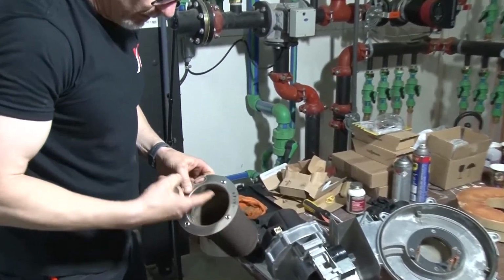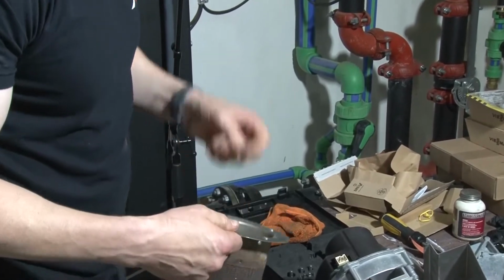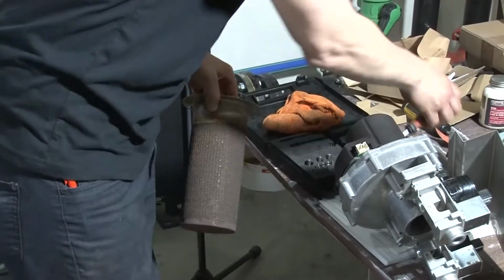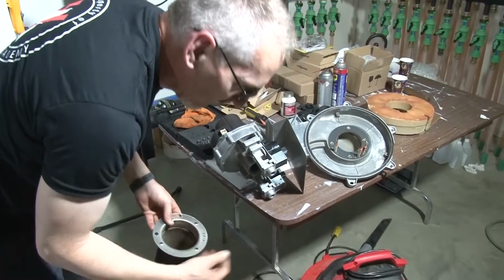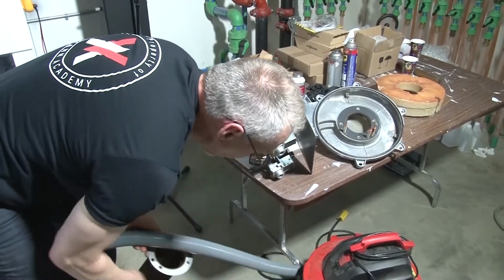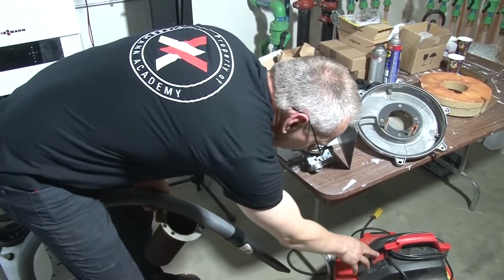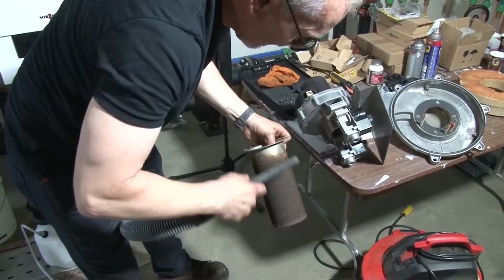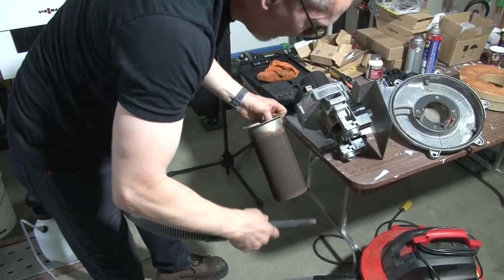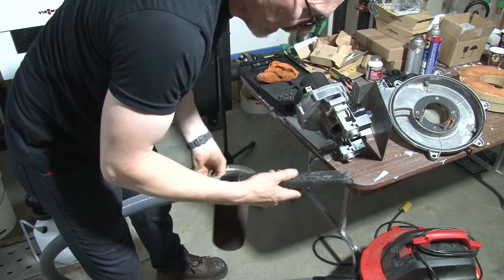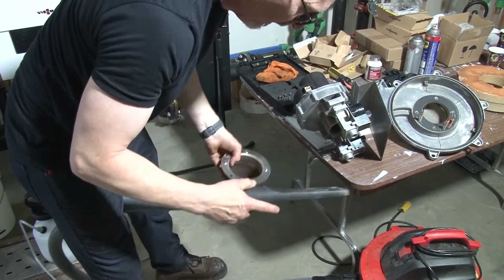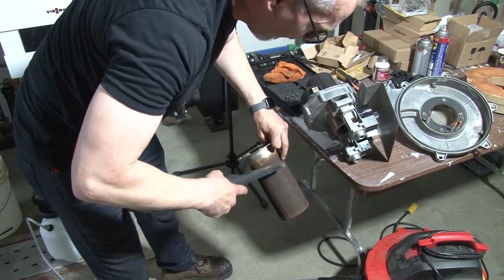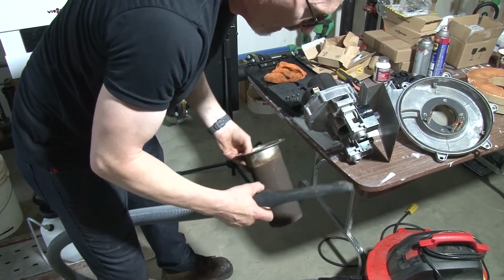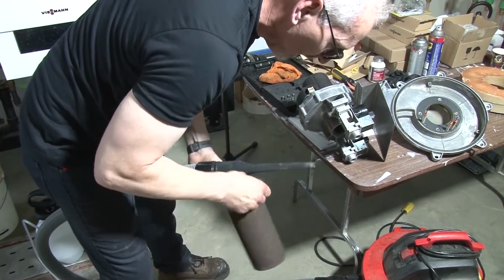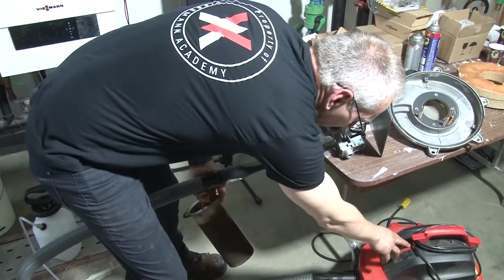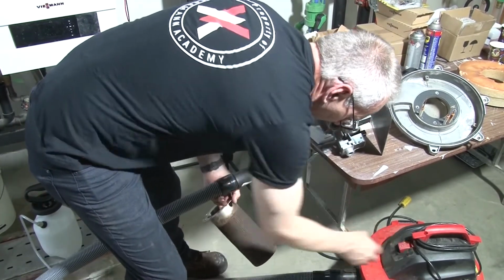So when we have this out, there's a little bit of debris in here. We could take a vacuum, for instance, as I mentioned, and kind of vacuum through there. Or we can take some compressed air and give it a little bit of a cleaning. Now when you're using a vacuum, the idea is not to sit there and scrub into that. You're just lightly going over that. Sometimes a brush style of connection is a little bit better. It gets in there a little bit better. But gentle is really the name of the game. These are, like I say, a sensitive area of the boiler. We want to make sure that we take care of it.